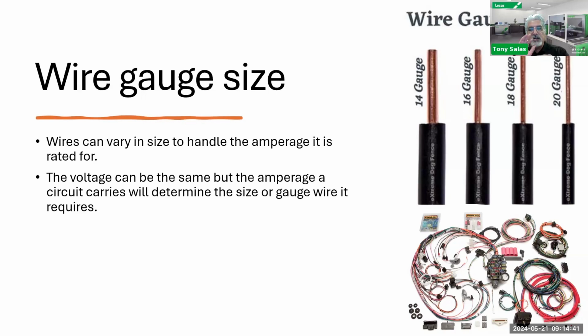But if that alternator is pushing that voltage, pushing that amperage, and it's struggling to because the gauge is so small, that's going to cause a lot of work, and it could heat up that alternator and eventually shorten its life. So when you see situations where we have repetitive failure after 3 months, 6 months, a year of an alternator or generator, it often begs the question: is it because we're working with very underwired circuits there?